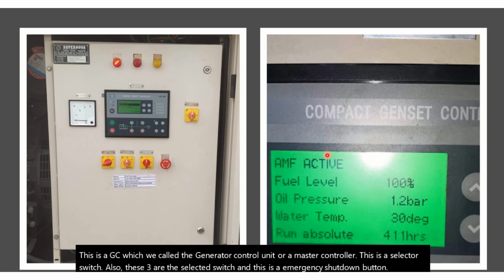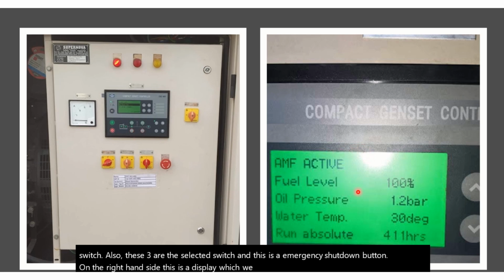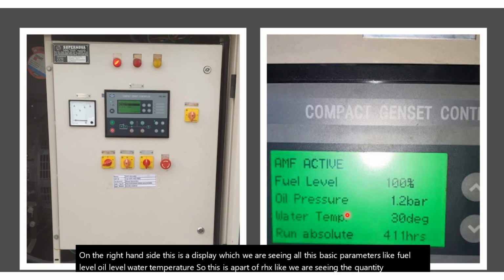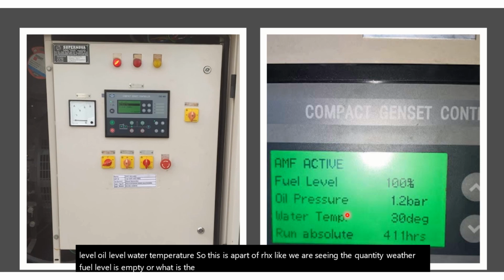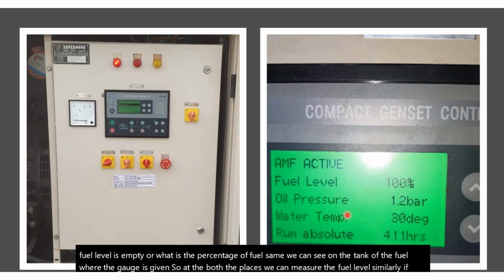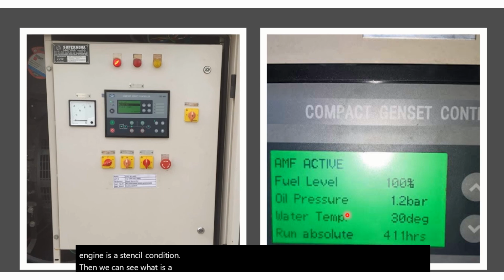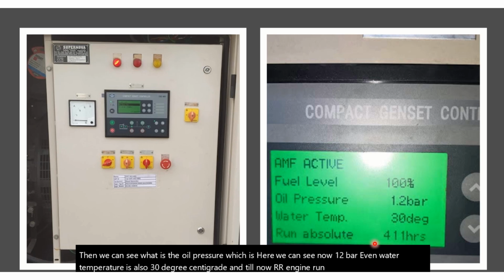On the right hand side, this is a display in which we see all the basic parameters like fuel level, oil level, and water temperature. This is a part of our A checks. We see the quantity, whether the fuel level is empty or what the percentage of fuel is. The same we can see on the fuel tank, where a gauge is given, so at both places we can measure the fuel level. Similarly, if the engine is in a standstill condition, we can see the oil pressure, which is now 1.2 bar. The water temperature is 30 degrees centigrade, and till now our engine run hour is 411. So at every maintenance visit, all these basic parameters have to be noted down in the maintenance register.